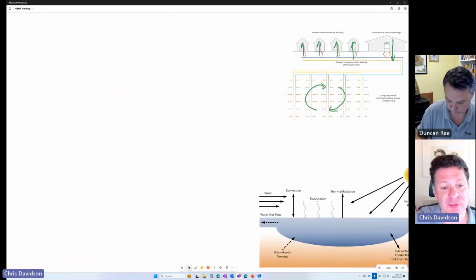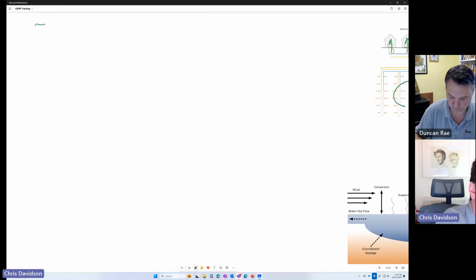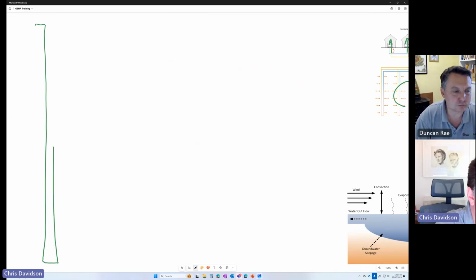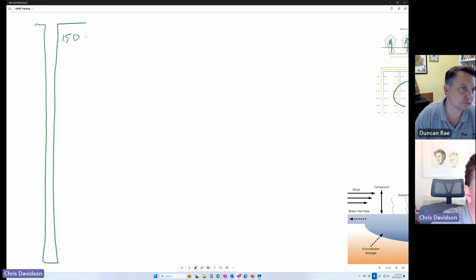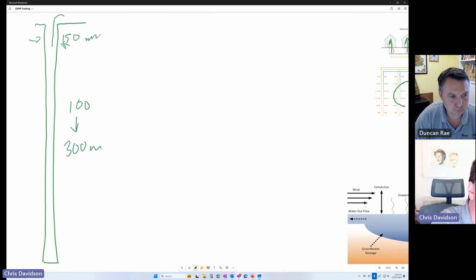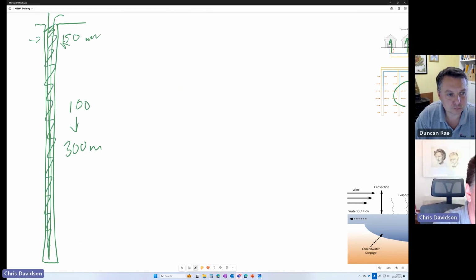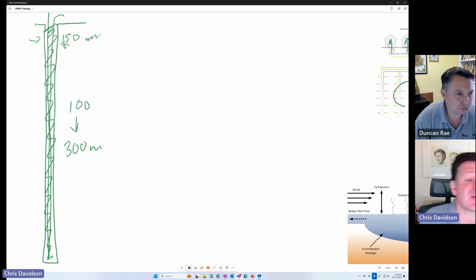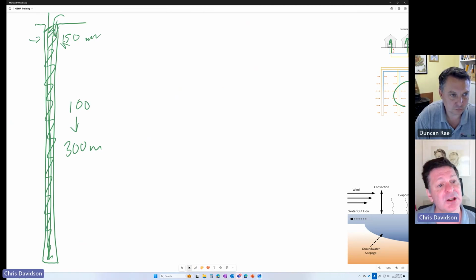Okay, so I've so far talked about closed loop boreholes. So what are they? Closed loop boreholes are very simple in construction. They tend to be about 150 millimeters in diameter across. They tend to be most commonly 100 to 300 meters deep. And most of the time they've got a single U-tube of polyethylene pipe installed in them, and then that's completed with a grout material. Now that grout material is there to do two things. One is to protect the ground so that no pollution, for example, could get down that borehole. So it seals off, provides a sanitary seal for the borehole, but also it provides thermal contact for energy to flow to and from that borehole. So that's the most common solution for commercial ground source systems.